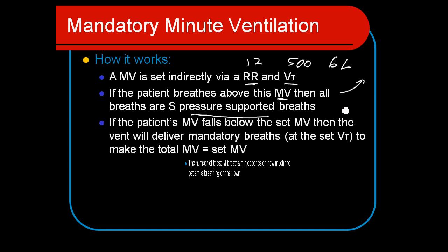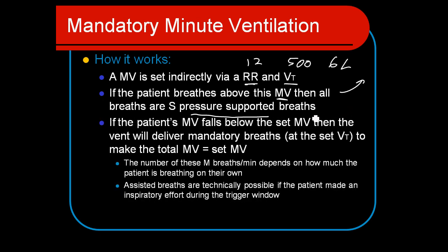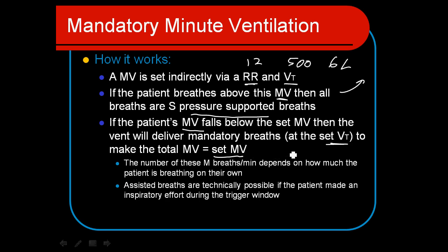The moment the patient drops below that minute ventilation requirement, the ventilator will kick in to deliver that set tidal volume and give enough breaths to ensure the patient meets that set minute ventilation requirement — in this case, six liters.